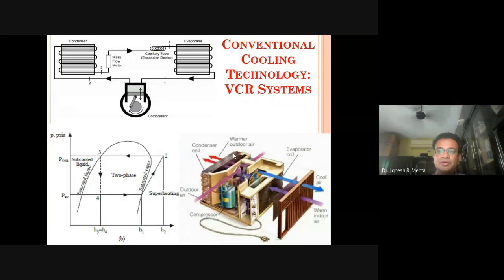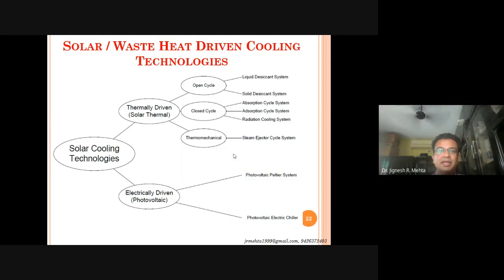So we are now starting our talk about the cooling application using the solar thermal collectors. This is the vapor compression refrigeration system. The components, cycles and hardware are known to us. And if you want to use solar heat or waste heat for cooling, the type of systems are different. So those type of systems have been illustrated here. Solar driven, solar thermal, it can be open cycle, closed cycle, or thermomechanical.